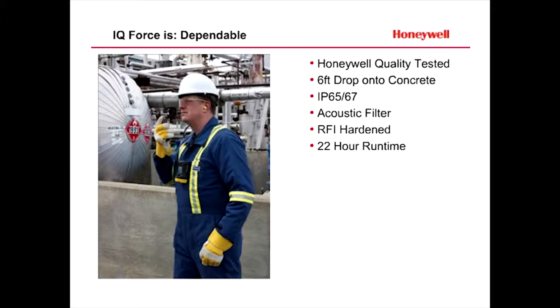We've also designed for customers working in extremely dusty environments with an acoustic filter to protect the buzzer. So no matter what, you're not going to lose volume because of dust getting into the sounder. One of the major causes of false alarms in industrial spaces is interference from two-way radios. Nobody wants to have to deal with false alarms. On top of the lost productivity that comes from these false alarms, these cause people to lose trust in the instrument. So we made sure the IQ Force was RFI hardened. We test with the most powerful licensed radios in a number of different bands, from UHF, VHF, and the 2.4 gigahertz space to make sure there's no false alarms or fail-unsafe modes.